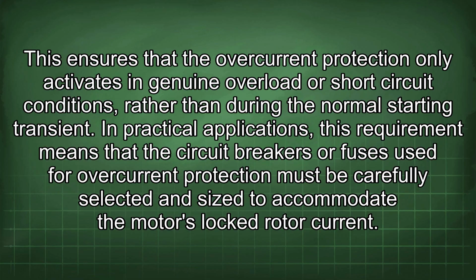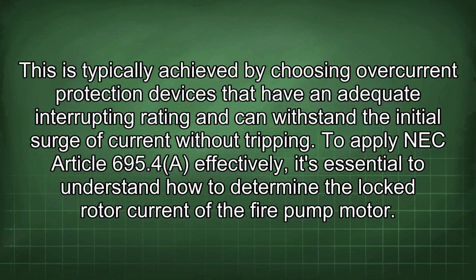In practical applications, this requirement means that the circuit breakers or fuses used for overcurrent protection must be carefully selected and sized to accommodate the motor's locked rotor current. This is typically achieved by choosing overcurrent protection devices that have an adequate interrupting rating and can withstand the initial surge of current without tripping.